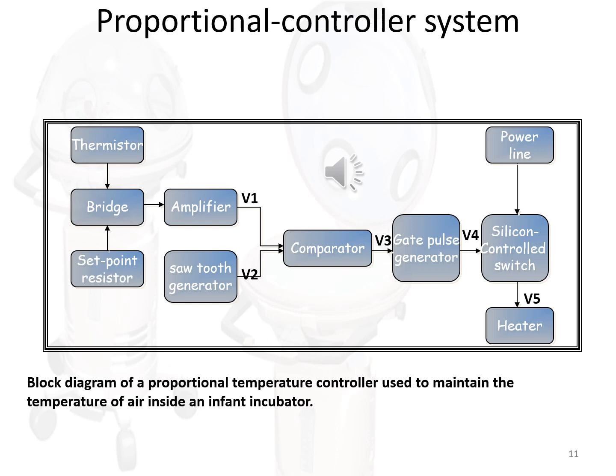The amount of power applied to the heater is proportional to the difference between the actual air temperature and the set point. This means that the amount of power decreases as the temperature approaches the set point. Some incubators use the skin temperature of the infant, and the controller is set to maintain the infant's skin at a given temperature.